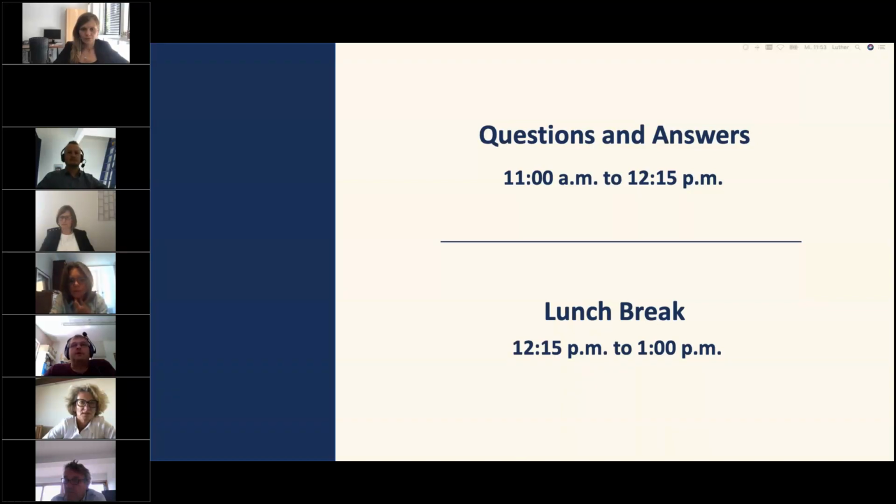Yeah. I mean, this goes a little, oh, sorry. In fact, I just wanted to add that this makes the difference between the method and the intended purposes of the device that is put on the market. So we have to keep this in mind when making the classification of the device. Yeah. And like I said in my talk, aid to diagnosis or an absolute diagnosis affects the type of studies you do and the level of clinical evidence. It doesn't necessarily impact on the class.